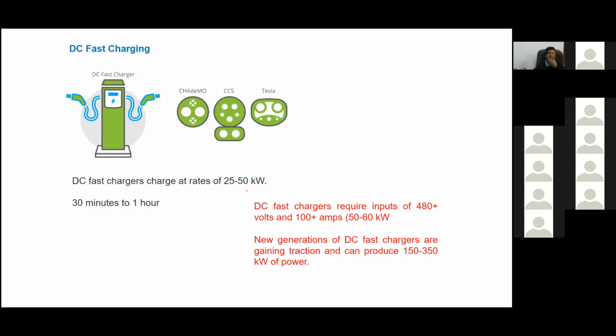Here you can have very high power charging, directly giving DC, and the fast charger can range 20 to 50 kilowatt. Even for charging an electric bus or electric truck battery, it can be 80, 90, or 100 kilowatt, with voltage levels more than 480 volt - 480 or 600 volt DC, and current around 100 ampere. So 480 DC voltage times 100 ampere DC current, V into I, is approximately 50 to 60 kilowatt power. These are the DC chargers.